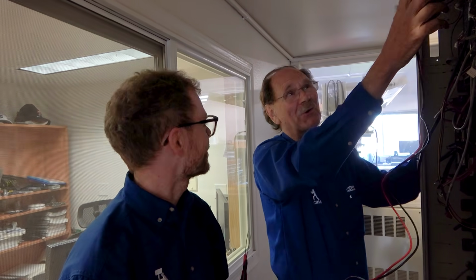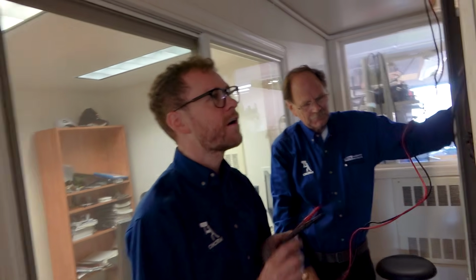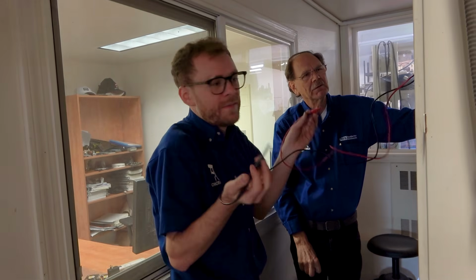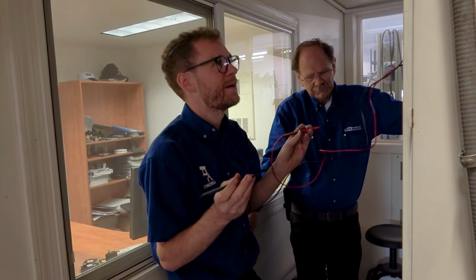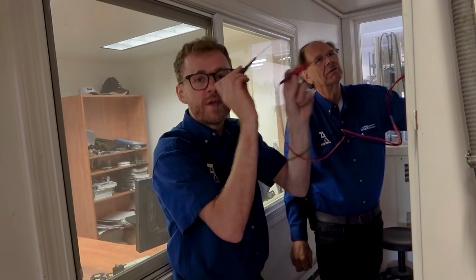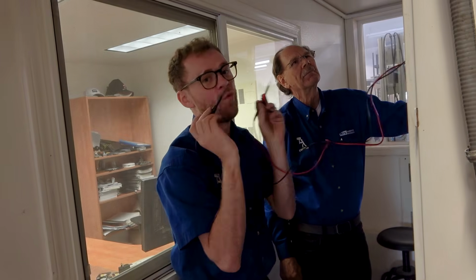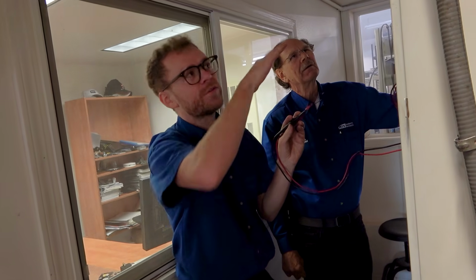I got the picture of the lightning bolts coming off of the arc. What I have seen, this happened down at Airway Heights here. The machine would randomly alarm out, and we were there one day troubleshooting it. We had been there 4 or 5 times. We'd get there, the problem wasn't happening. And we were poking, and we saw some arcs. And we went, wait a minute. Turn off the breaker, check the power was off, tightened on every connection. Multiple connections were loose. Yeah, loose wires. So that's something to keep in mind.